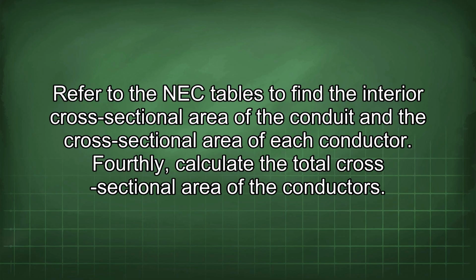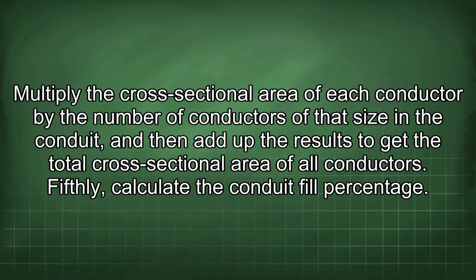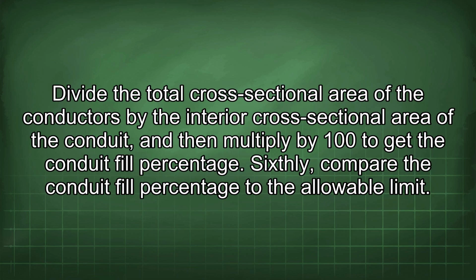Thirdly, look up the cross-sectional area of the conduit and conductors. Refer to the NEC tables to find the interior cross-sectional area of the conduit and the cross-sectional area of each conductor. Fourthly, calculate the total cross-sectional area of the conductors. Multiply the cross-sectional area of each conductor by the number of conductors of that size in the conduit, and then add up the results to get the total cross-sectional area of all conductors. Fifthly, calculate the conduit fill percentage. Divide the total cross-sectional area of the conductors by the interior cross-sectional area of the conduit, and then multiply by 100 to get the conduit fill percentage.